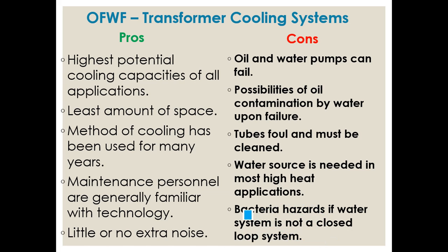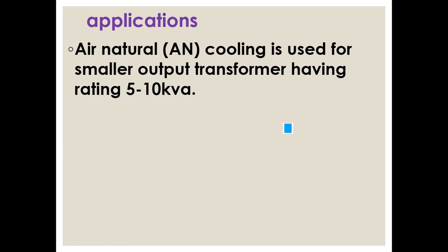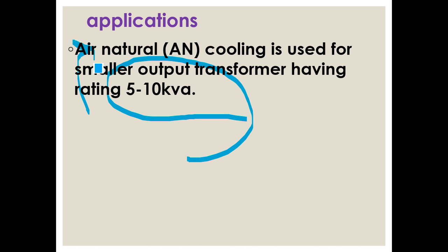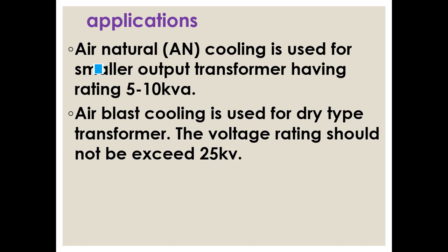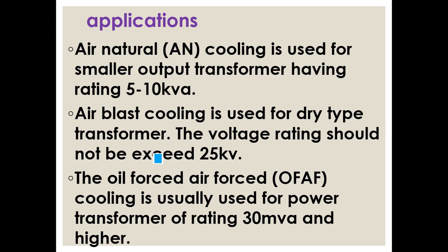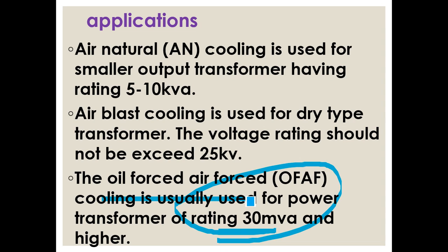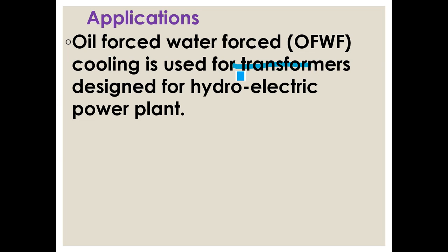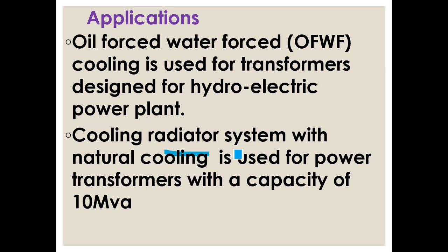Application summary by capacity: Air natural (AN) cooling is used for 5 to 10 kVA transformers. Forced air cooling is used for capacities greater than that, with voltage ratings typically not exceeding 25 kV, so 11 kV transformers use this directly. OFAF is used for 30 MVA and higher applications. OFWF is used in hydroelectric power plants because water availability is there. Cooling radiator systems with natural cooling are used for power transformers with 10 MVA and above.